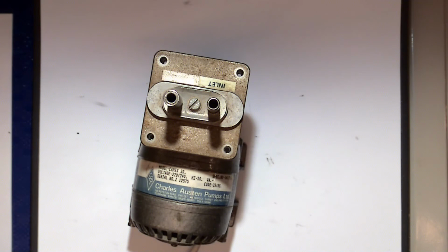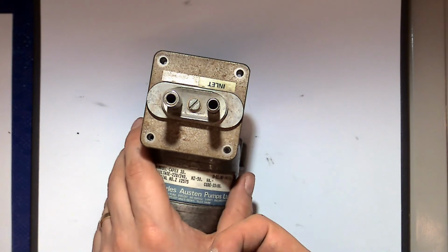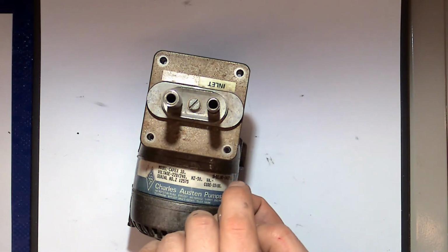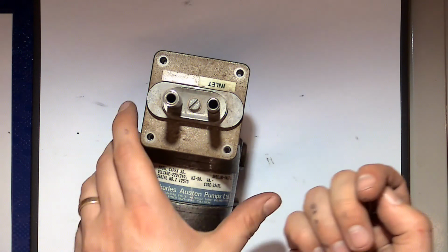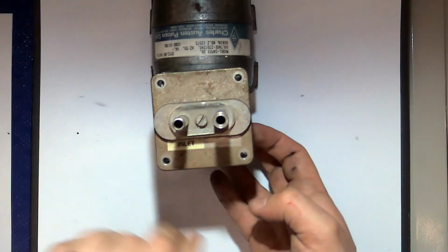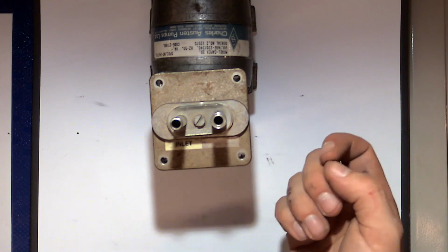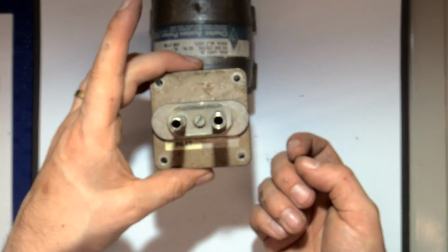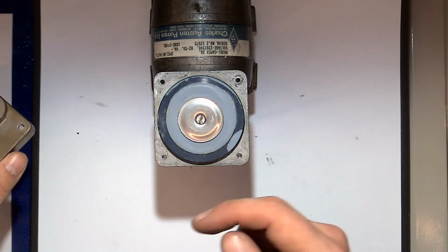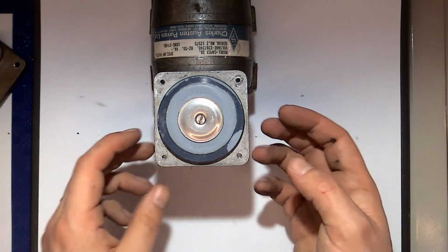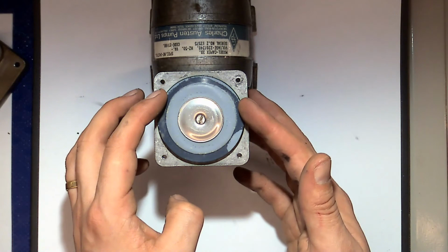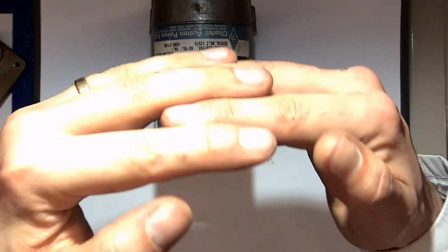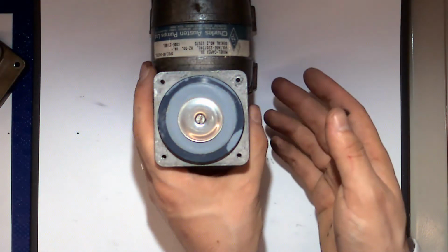Okay, moving on now to the diaphragm style pumps. Again, the motor at the rear and the pump section at the front. In this case, inlet and outlet are both at the top. Well, inlet is blank, you can assume that this side used to say outlet. If I remove this head, you'll see the top of a piston. It's a very short travel piston, and the whole thing doesn't move, therefore it's a diaphragm. It kind of bulges like that.